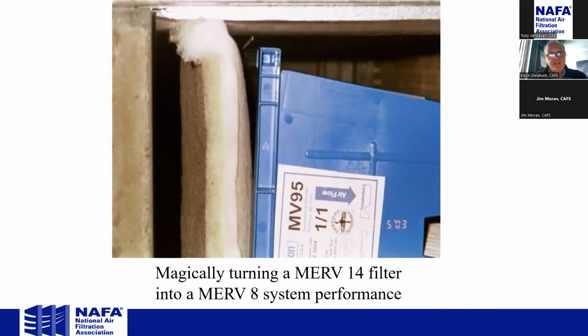Okay. In this situation, this is probably a MERV 16 or MERV 17 filter, very high expensive. Probably $175 Canadian. So I don't know what that makes American, but it's an expensive filter that's not sitting in the U channel. The U channel does not extend far enough to actually hold the filter in place. So because these filters are high efficient and have quite a bit of pressure drop on it, you're going to have an inordinate amount of air want to bypass that filter and go around it. And what we've technically done is reduce the filter performance in here. In this case, it says a MERV 14 to a MERV 8 filter system. So you're paying for a MERV 14 filter system, but you're actually only getting performance in the MERV 8 just because the filter doesn't sit in the channel. The channel doesn't extend far enough to hold that filter securely in place.